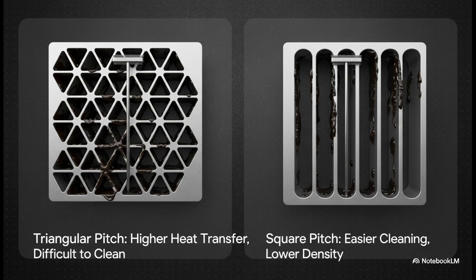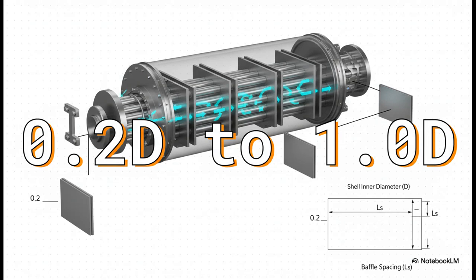Now, if you're in a refinery dealing with dirty crude oil that you know is going to cause fouling, that ease of maintenance often makes the square pitch the winning choice, even if it means you end up with a slightly larger shell. It's all about trade-offs. Now let's talk about the baffles. Their whole job is to force the fluid on the shell side to flow across the tube bundle, not just along it, which is way better for heat transfer.